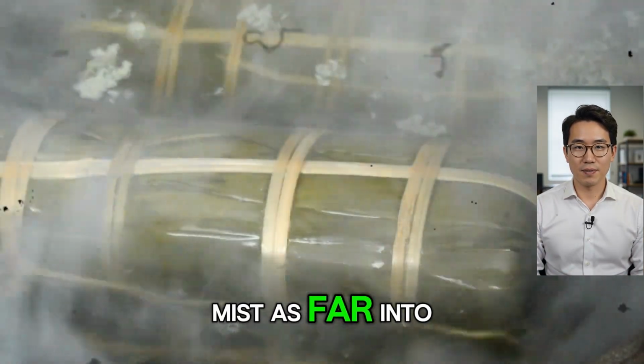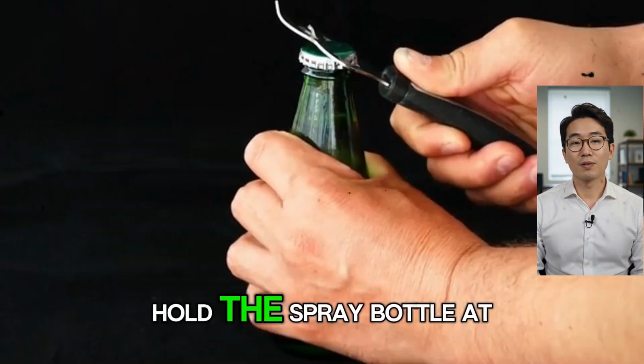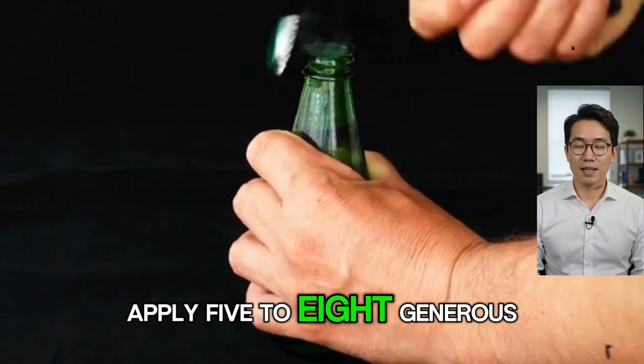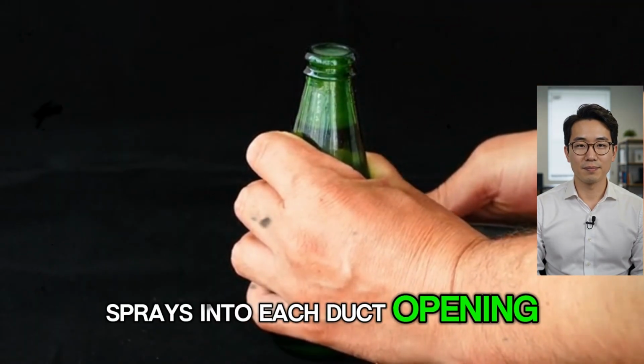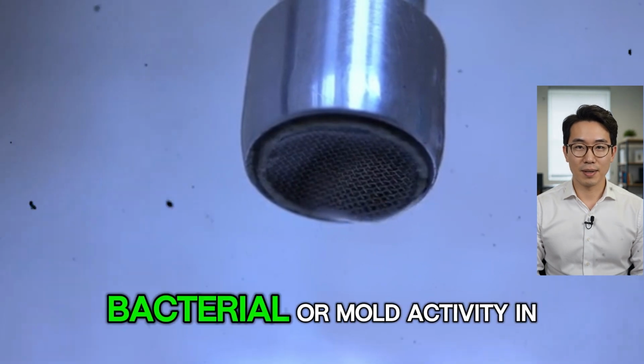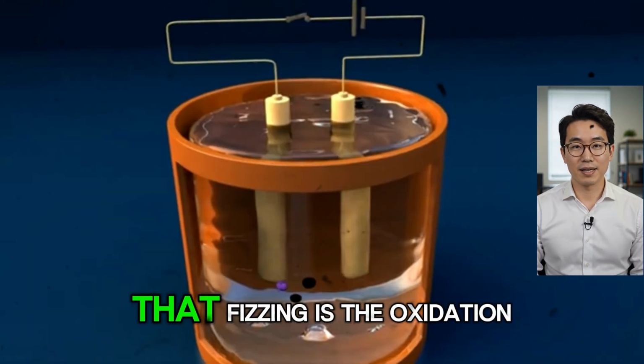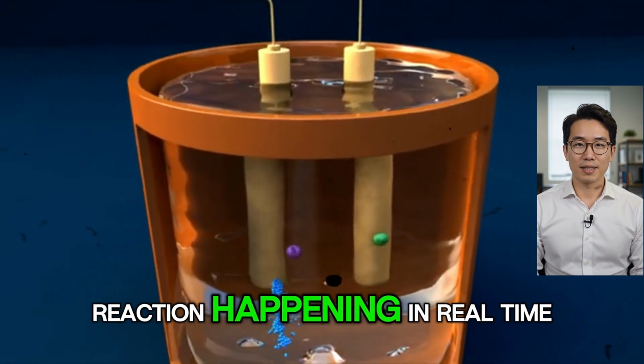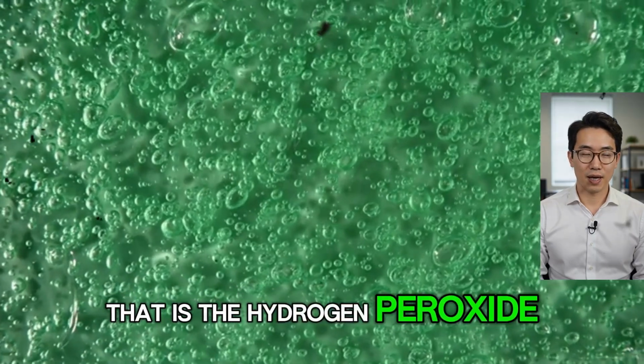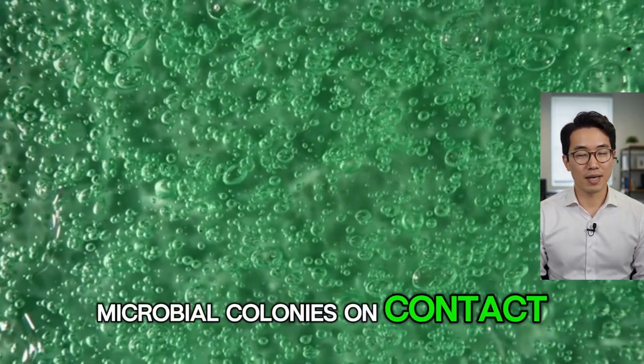You want to get that mist as far into the duct as possible. Hold the spray bottle at an angle and apply 5 to 8 generous sprays into each duct opening. You will hear the faint fizzing sound if there is bacterial or mold activity in there. That fizzing is the oxidation reaction happening in real time. That is the hydrogen peroxide destroying the microbial colonies on contact.